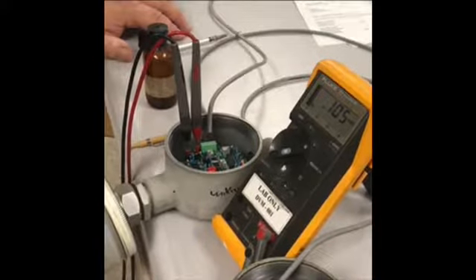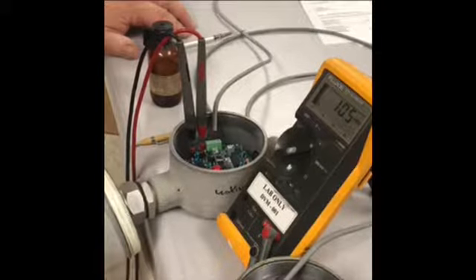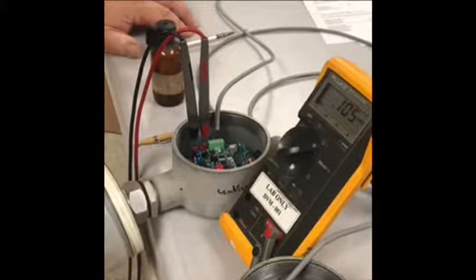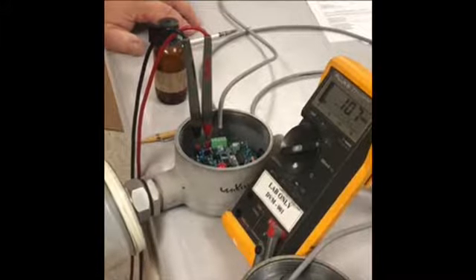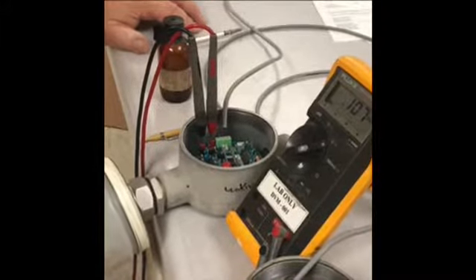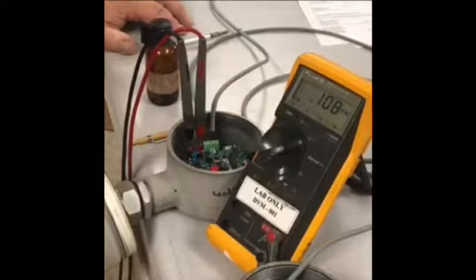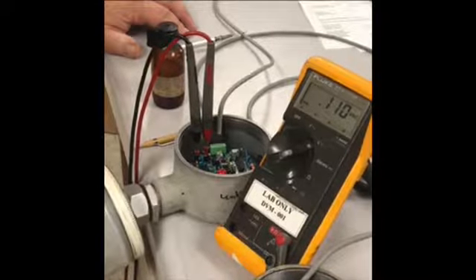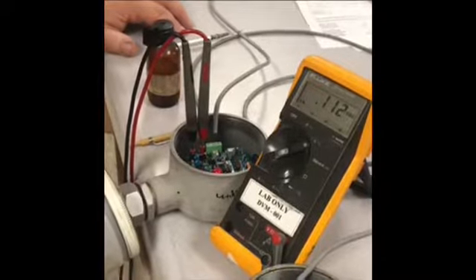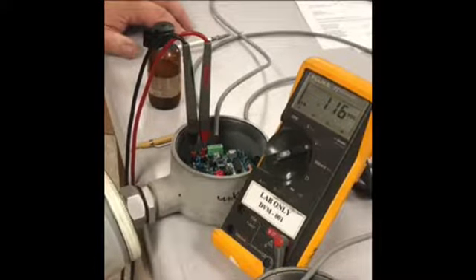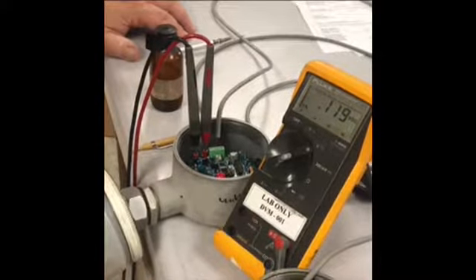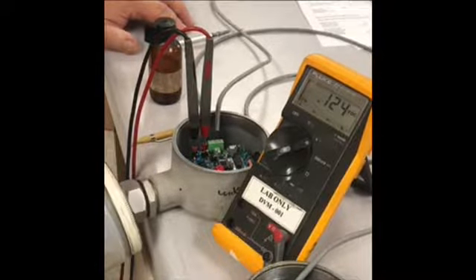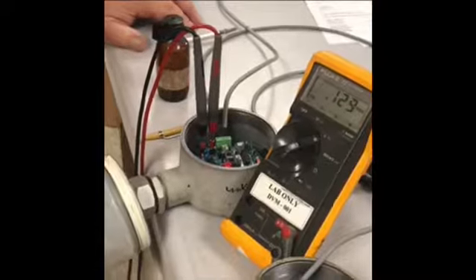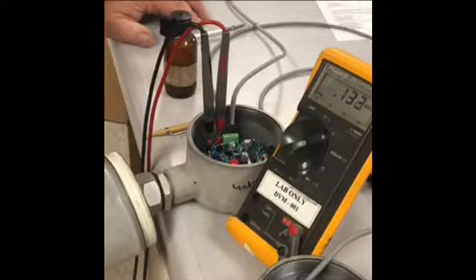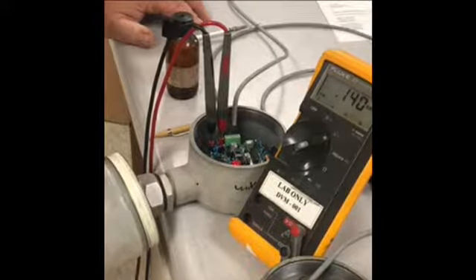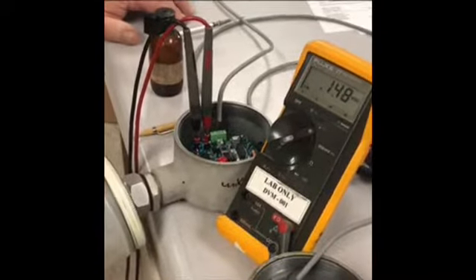With ammonia, there is a lag before it will start to read the gas. That's normal. Some gases read almost immediately. Ammonia does not. It will take some time for it to start to respond to the ammonia. Just go ahead and keep your eye on the voltmeter. At first it'll be a slow response. As you can see, it's starting to respond to it. It will start to get a little faster as it responds more and more to the ammonia. This could take 1 to 2 minutes to actually get a stabilized condition for this sensor, for this gas at 200 ppm. Higher concentrations definitely read better. They read faster.